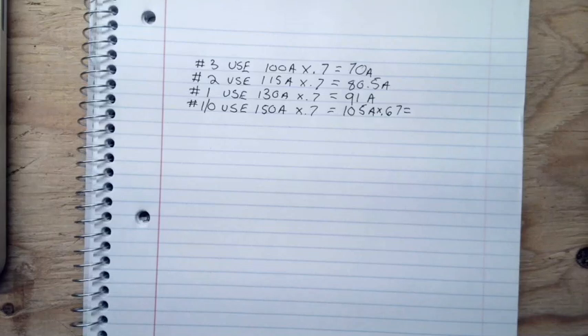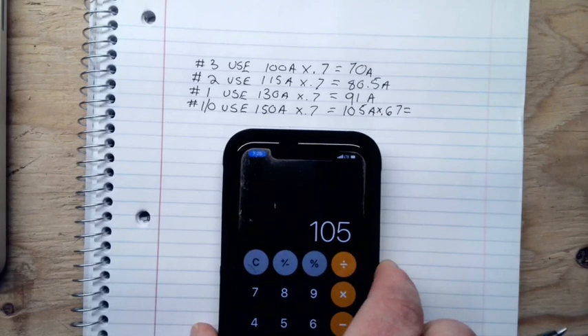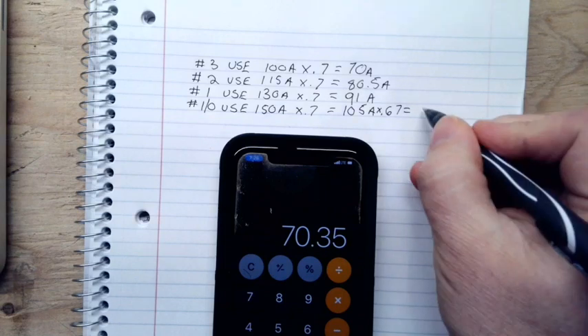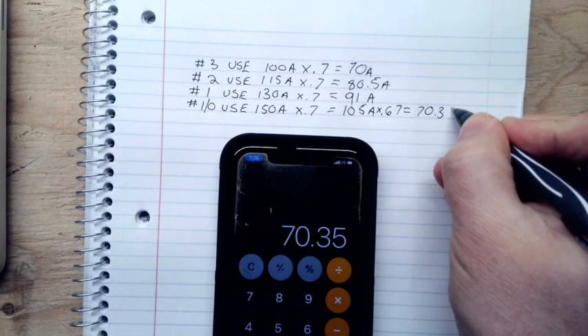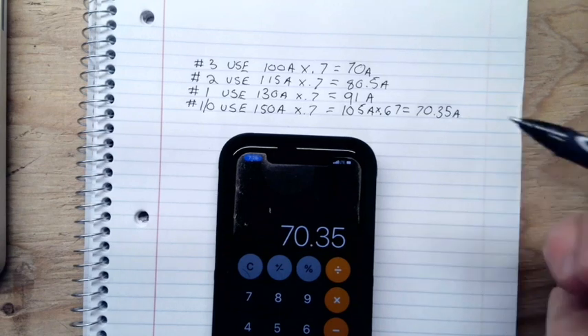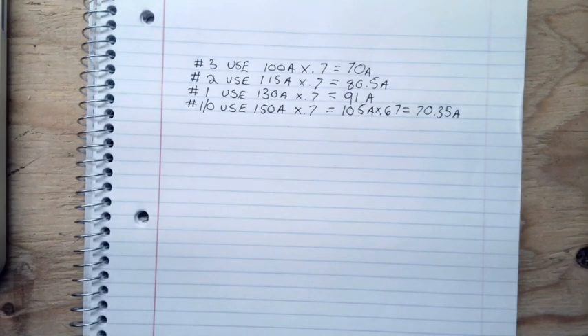So I'm going to come over to the 75-degree chart, and that's a 0.67 correction factor. So I'm only allowed to use 67% of this 105 amps we just found. So I got my 105, and now I'm going to multiply that by 0.67 equals 70.35 amps. Again, that's a far cry from the 100 we're looking for. So I got to keep going up. So I know that the next size is number two ought.